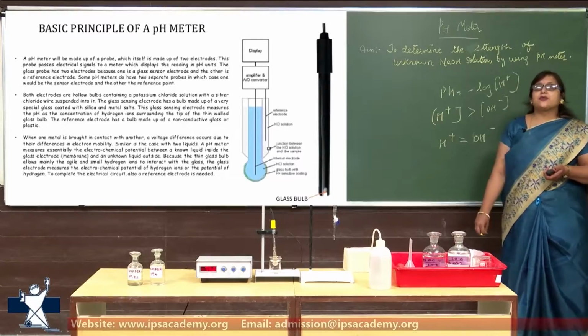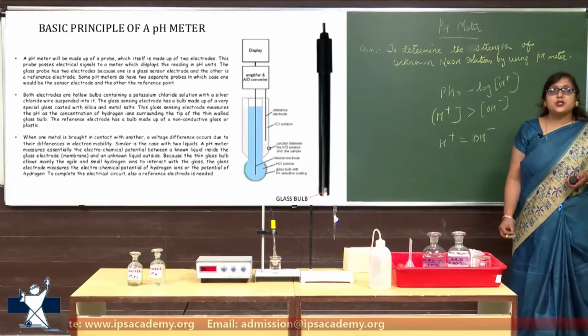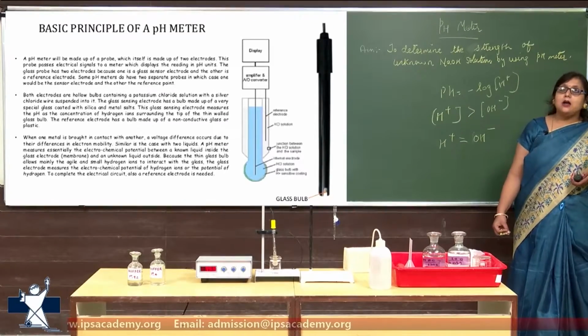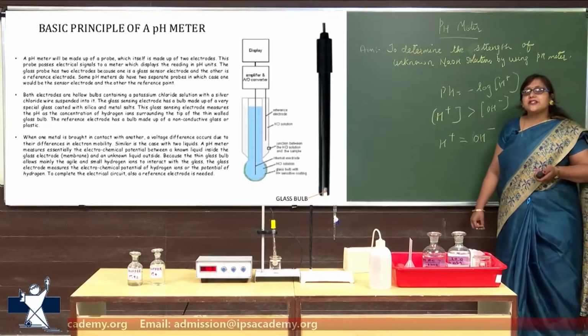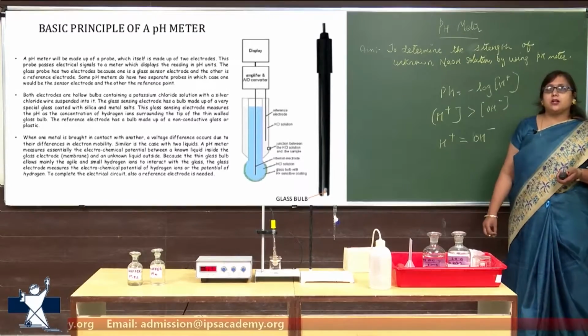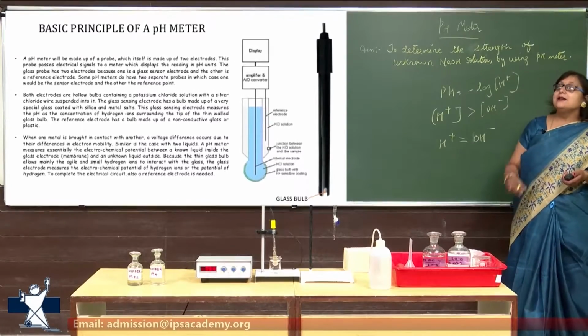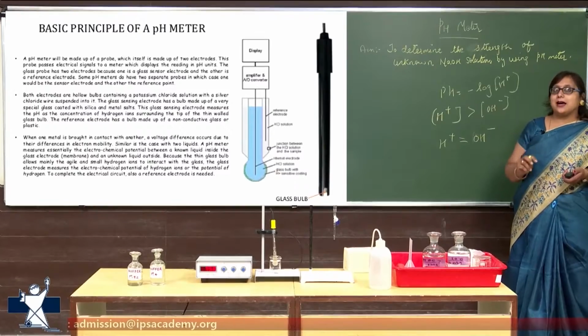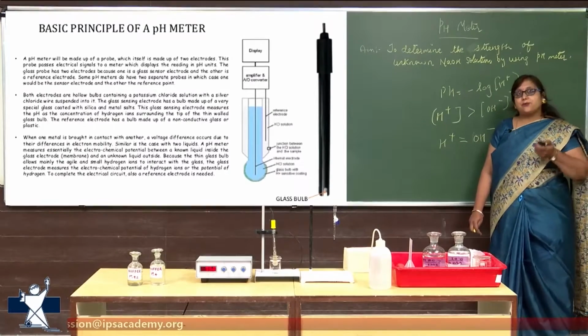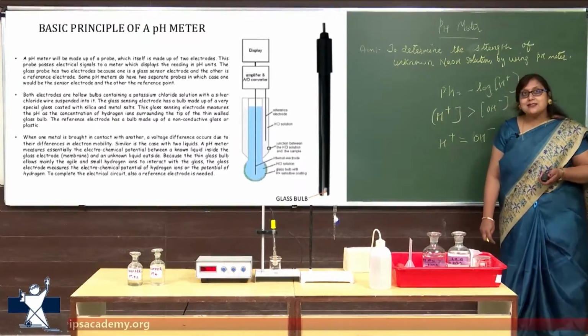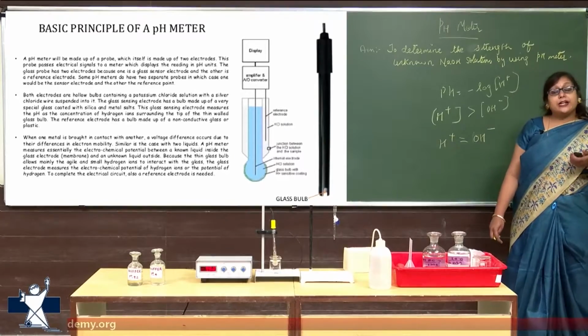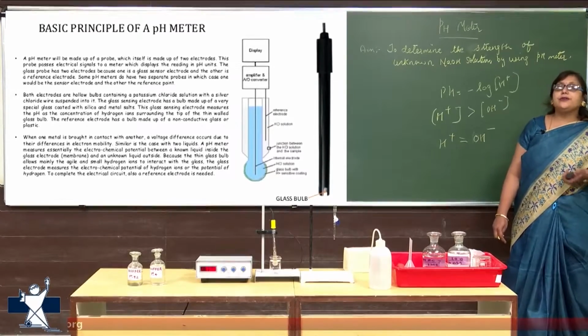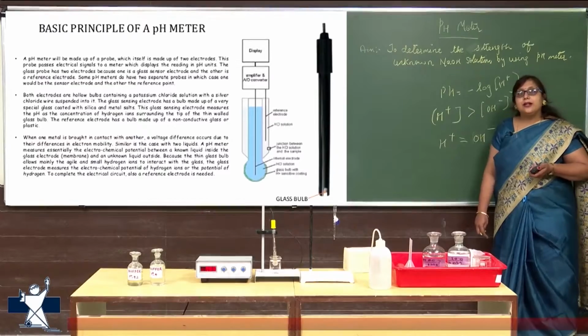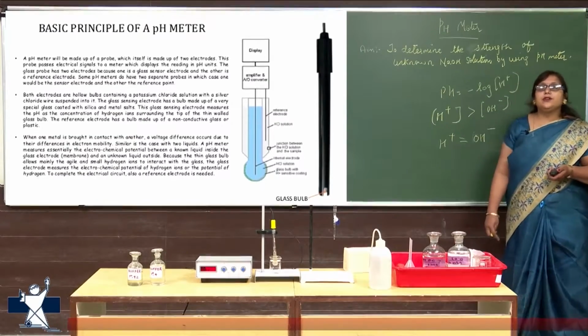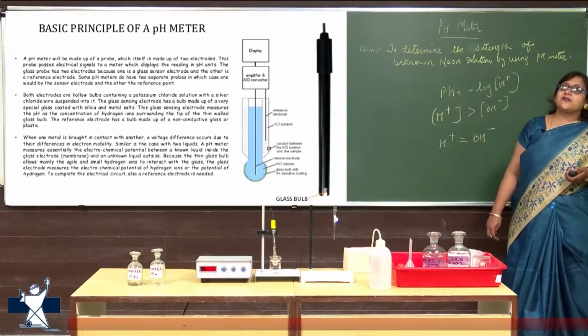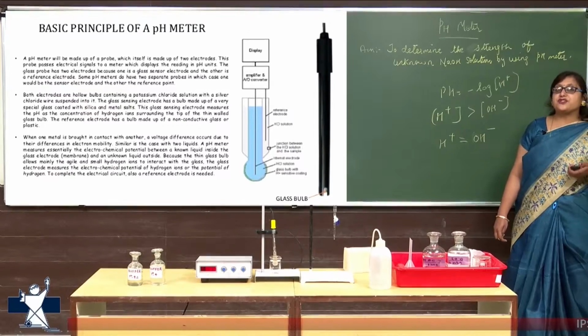the glass sensing electrode has a bulb which is made up of very special glass coated with silica or metal salt, and the glass sensing electrode measures the pH, the concentration of H ions surrounding the tip of the glass bulb. So, the reference electrode has a bulb made up of non-conductive glass or plastic material. So, it is not going to conduct any electrode or metal ion through it, but the glass electrode is going to conduct, and the glass electrode is responsible for sensing the concentration of hydrogen ion.